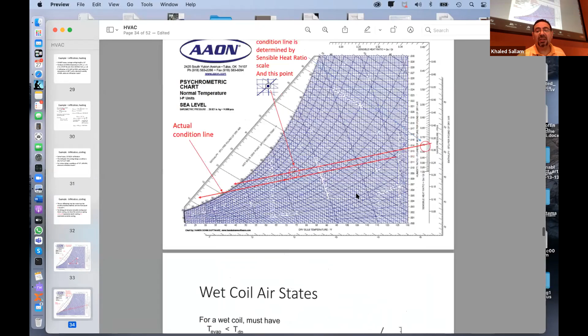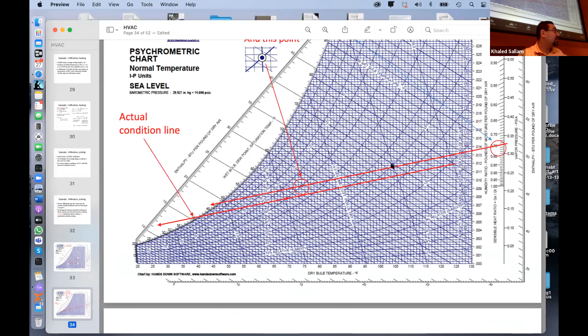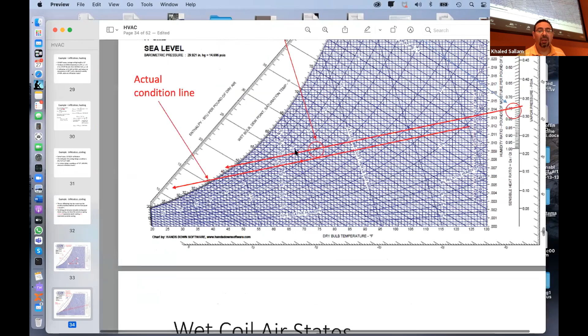Okay, so because it is 0.75 on that scale, if you put air in the room, the air will follow that line. So if you want to end up here, because that's the design condition, you need to supply air for them along that line. What is that line? This one is parallel to this guy. Why did I use this guy? Because that's where this point is. This is where I can use that chart.